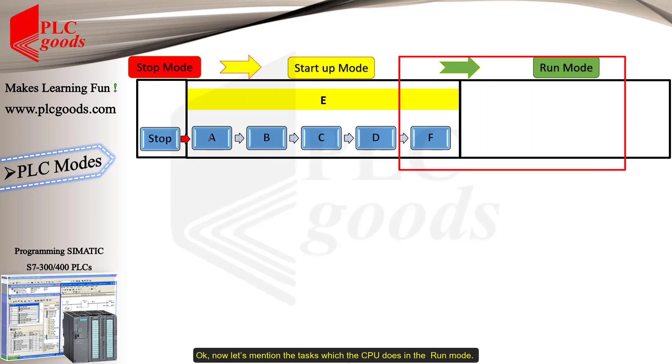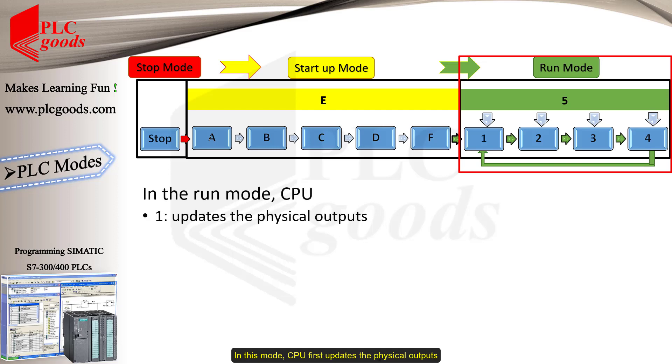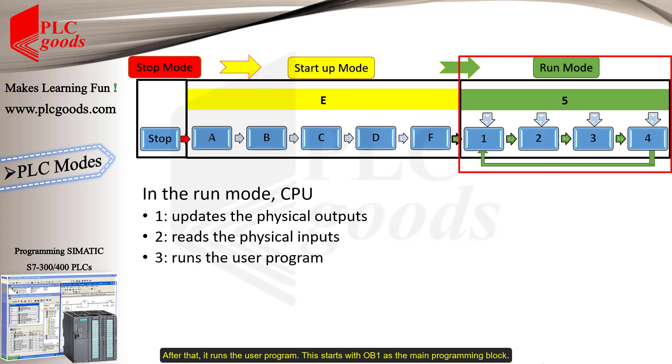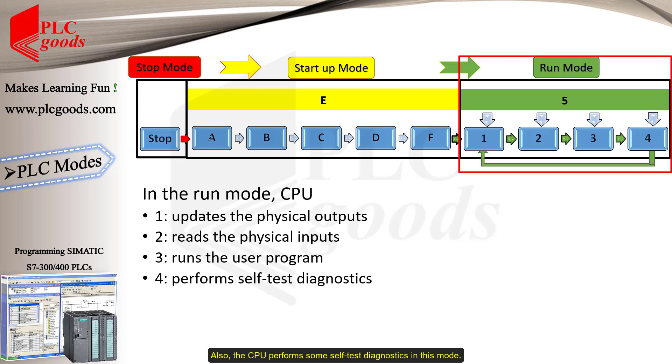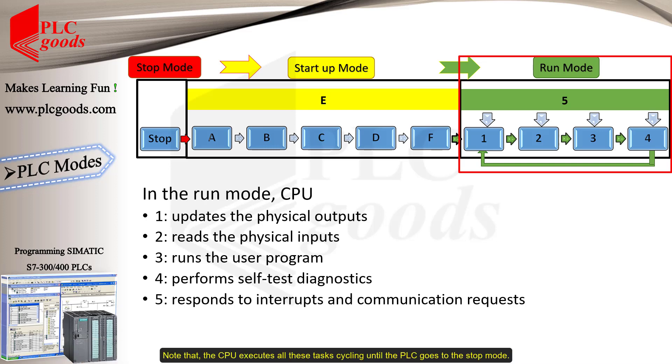Okay, now let's mention the tasks which the CPU does in the run mode. In this mode, CPU first updates the physical outputs. Then, it reads the physical inputs and updates its input's image memory. After that, it runs the user program. This starts with OB1 as the main programming block. Also, CPU performs some self-test diagnostics in this mode. And every time an interrupt occurs, the operating system calls appropriate OB and then returns to the main program and responds to communication requests. Note that the CPU executes all these tasks cycling until the PLC goes to the stop mode.